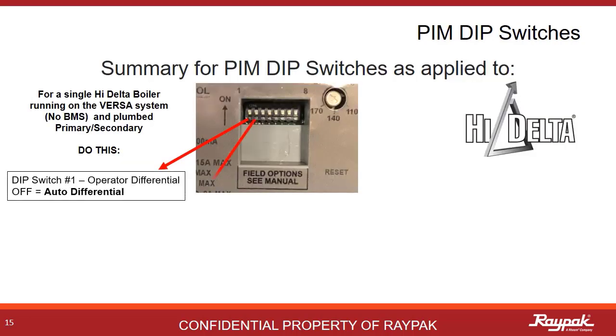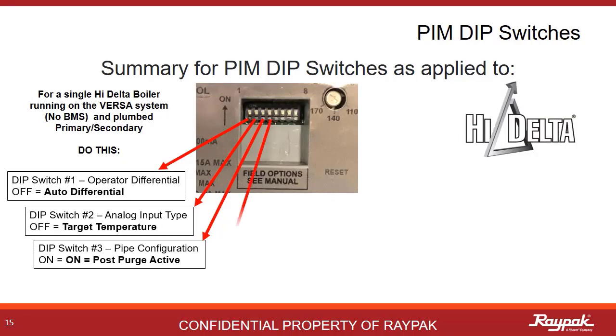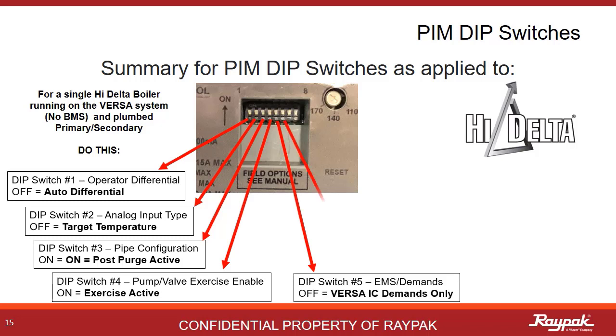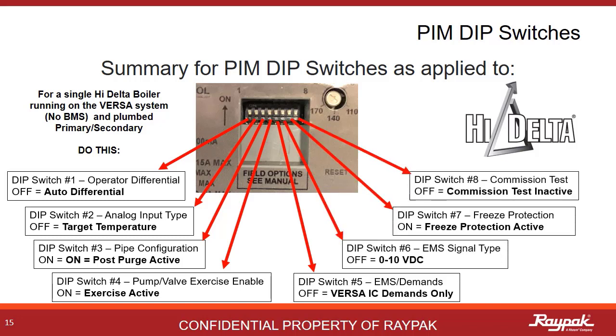Here is a summary for PIM dip switches on Hi Delta boilers. For a single boiler operating on the Versa system — not on a building management system — and plumbed properly with primary-secondary plumbing, turn on dip switches three, four, and seven. Leave the others off. This will enable the post purge feature, allow for pump exercise, and enable freeze protection. Again, turn on three, four, and seven.